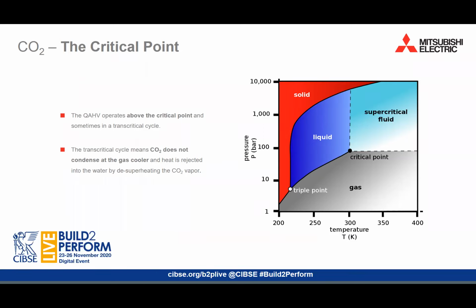This cycle is why it is so important to maintain the return temperature to the QAHV at as low a temperature as possible. If the return temperature into the gas cooler is high, then the ability to desuperheat the refrigerant is reduced, and so therefore is the capacity and COP.